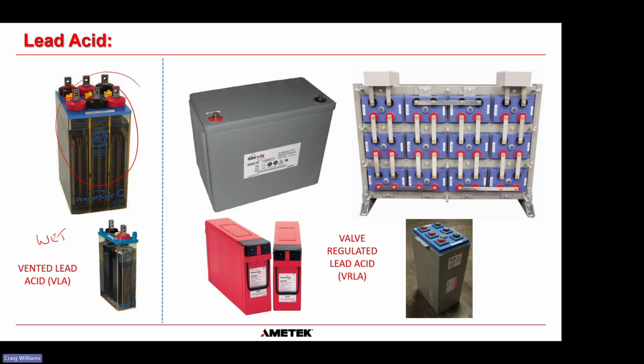But on the right-hand side, we have what are called valve-regulated lead acid batteries. They used to call them sealed batteries, but they're not sealed because they do have small valves. Every single one of these has a small valve that releases some pressure, some hydrogen out into the air. But what they try to do is recombine the hydrogen that's emitted back into the cell, so there is no loss in the electrolyte. That's why they were originally called sealed. So they're not actually sealed, but in normal operation they try to keep as much of the electrolyte inside the jar as possible.